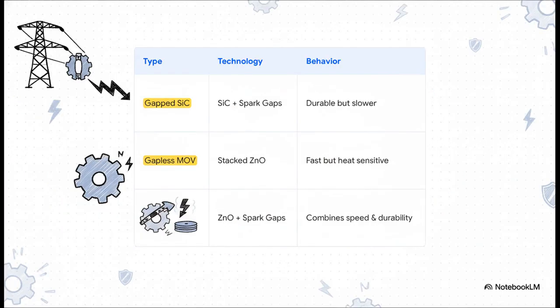But the real heavy lifters of the grid are the surge arresters. Think of these as high-speed, heavy-duty pressure relief valves for electricity, and they come in a few key types. There's the classic technology, which is really durable but a little slower. Then there's the modern MOV, or metal oxide varistor, which is incredibly fast but a bit more sensitive. And of course, engineers have combined the two to get the best of both worlds, speed and durability. Each one has a specific job to do in this invisible shield.